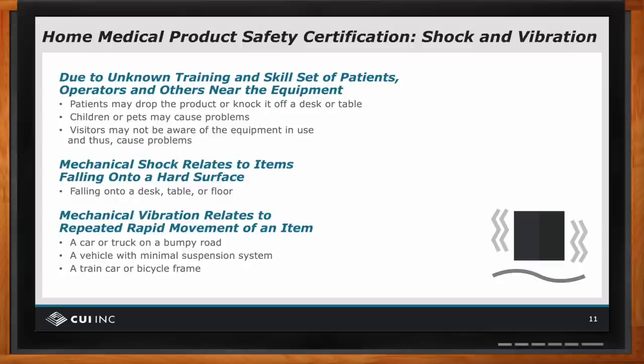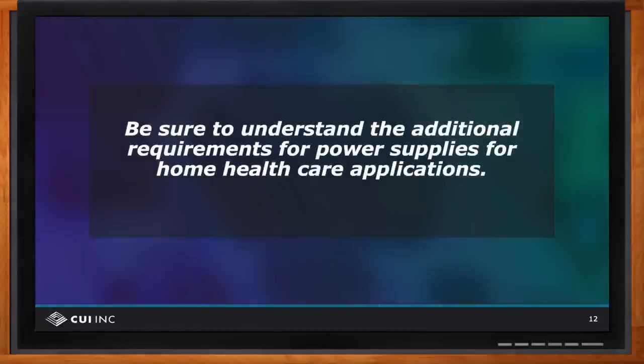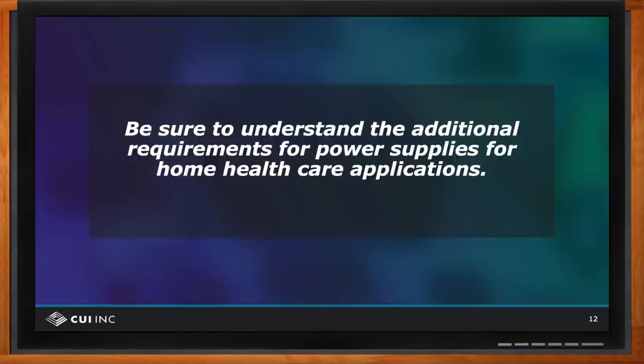The biggest takeaway is that we've been designing for commercial health care for many years, but especially following COVID and with cost-saving measures, there is a strong transition of health care into the home. When health care is provided in the home, trained personnel are not present. So while designs often still need to meet commercial medical requirements, there may be additional requirements for home health care. The design engineer needs to be certain they look at all home health care requirements and ensure they're meeting those if that's what their equipment will be designed for.